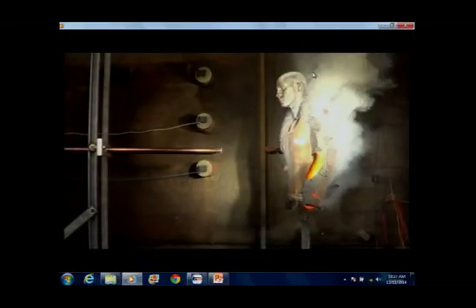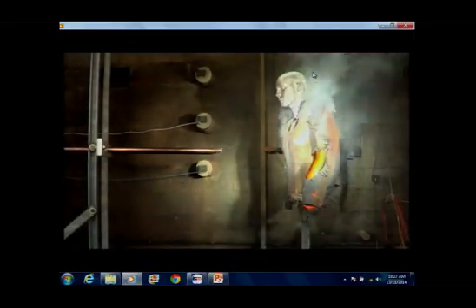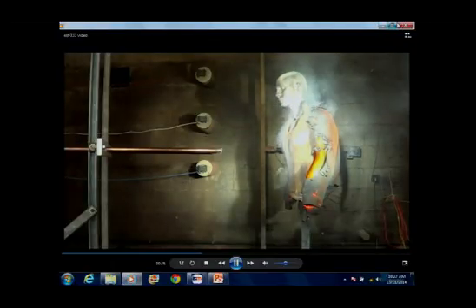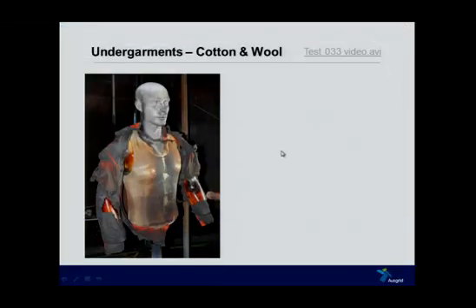I was expecting to see the cotton singlet on fire at this stage, and that's not what we got. A couple of reasons for that. By the time the arc-rated shirt is gone, the front of the cotton singlet is all charred, it's carbonised. So the front surface has carbon, the back surface has the torso, so there's very little oxygen getting to the uncharred cotton. So although there may be some risk, it would appear to be a low risk.